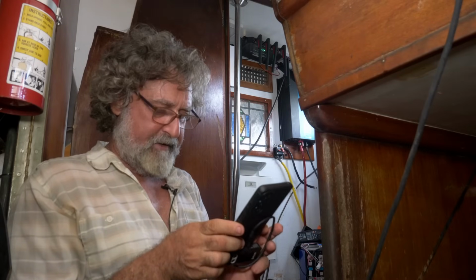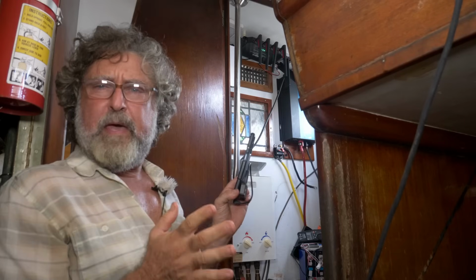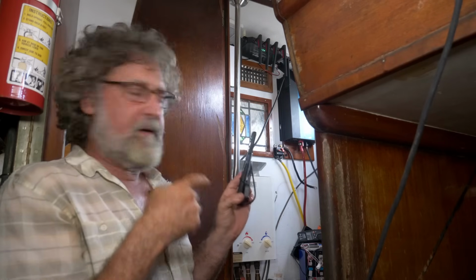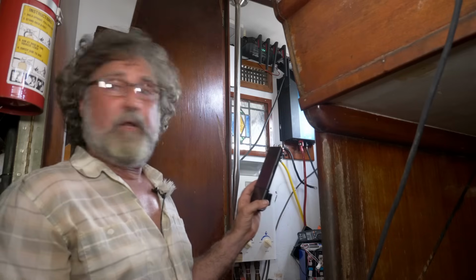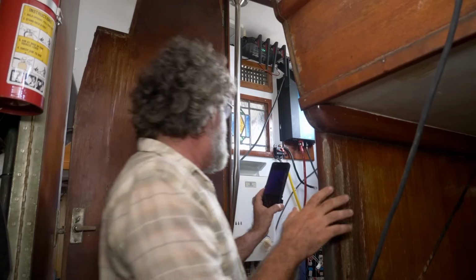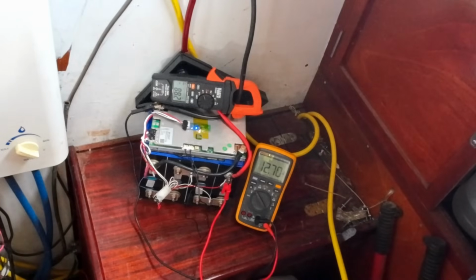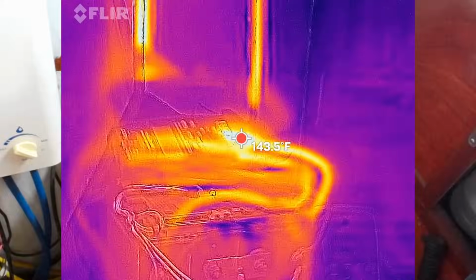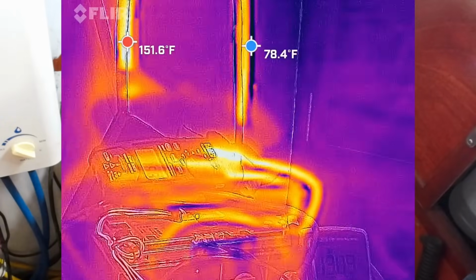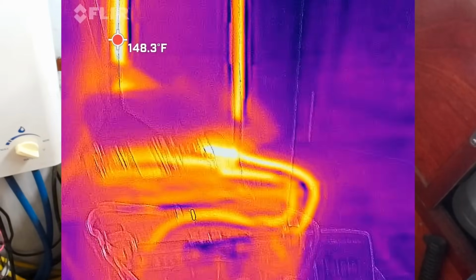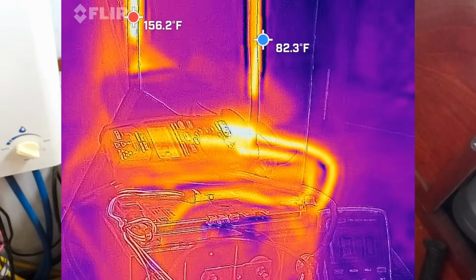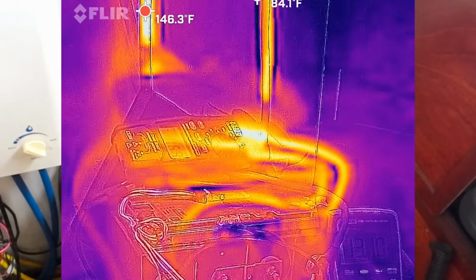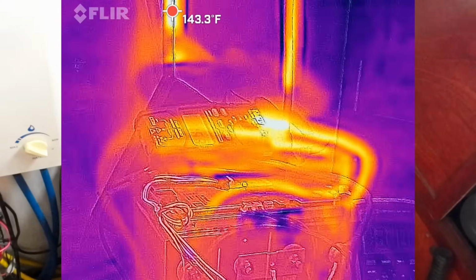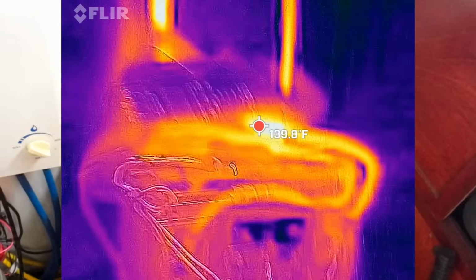So let's go back to the FLIR. It's been 6 or 7 minutes according to the timer here, and let's take a look at the temperatures. Same thing - hottest thing is the wires, and they're not that terribly hot. My wires going up to the device are much hotter than, or just as hot as, the wires in the device.